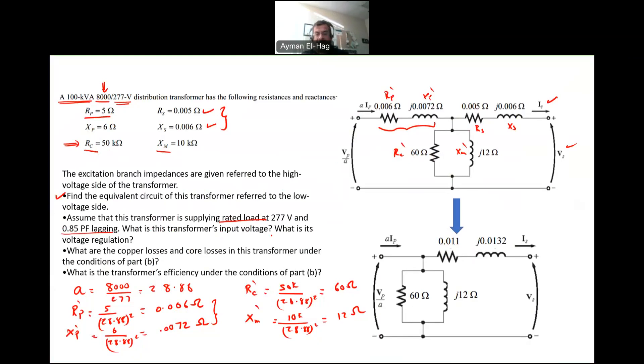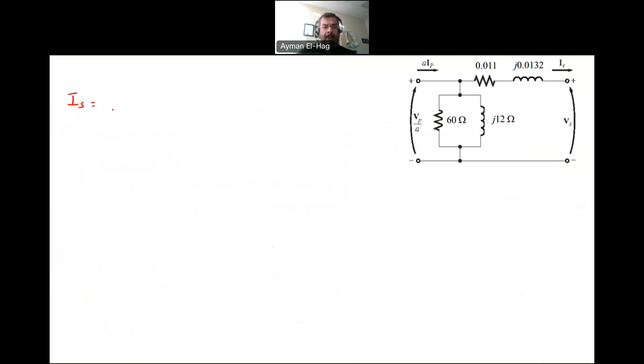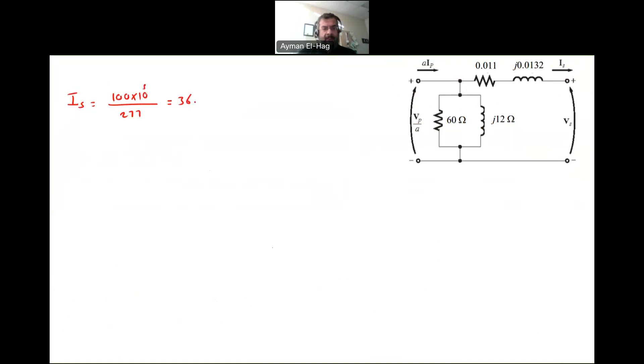The transformer input voltage will be VP over A — that is the input voltage, and VS is the output voltage. Now we want to find IS, the current in the secondary. The current will be the rated current, so we use the rated power — 100 kVA — divided by 277, which is the rated voltage at the secondary, and this will give me a current of 361 amps.